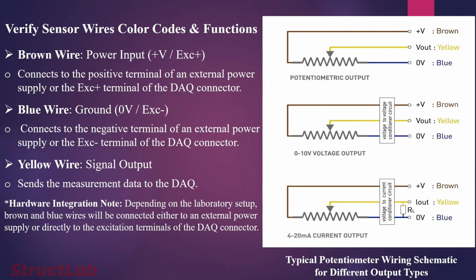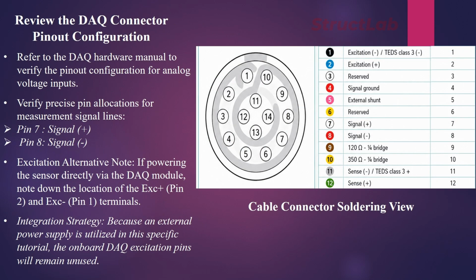Yellow wire. This carries the analog signal output, sending real-time measurement data straight to the DAQ analog input channel. Together, the brown and blue wires power the sensor, while the yellow wire feeds the measurement signal into your acquisition system.